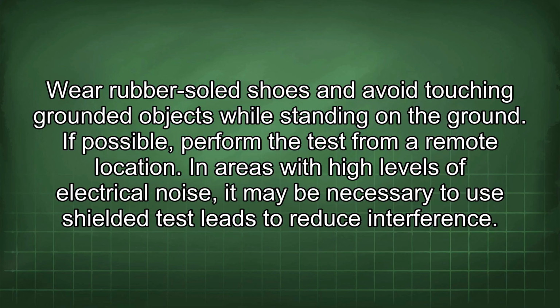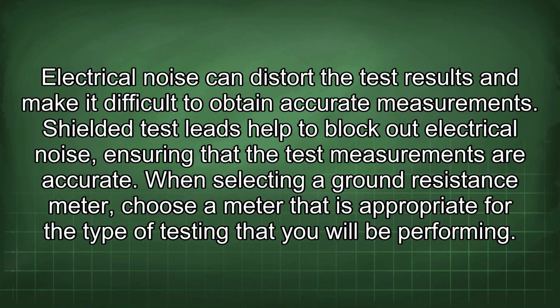In areas with high levels of electrical noise, it may be necessary to use shielded test leads to reduce interference. Electrical noise can distort the test results and make it difficult to obtain accurate measurements. Shielded test leads help to block out electrical noise, ensuring that the test measurements are accurate.